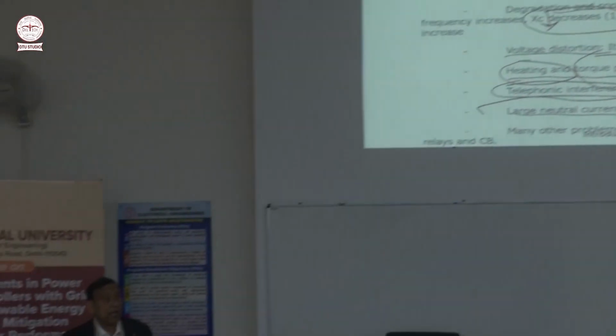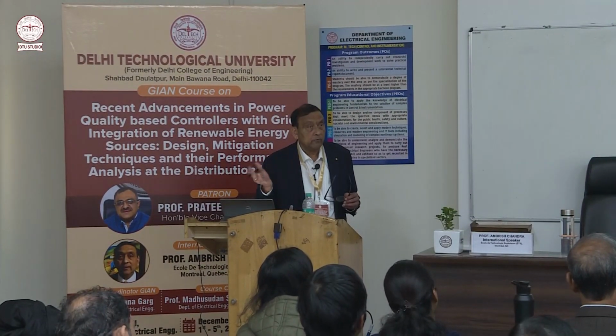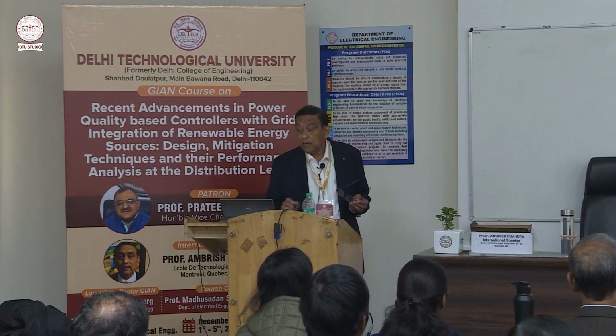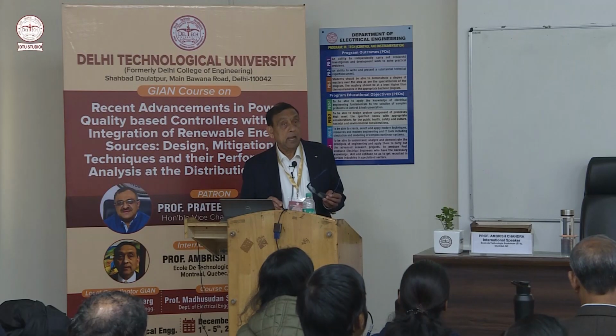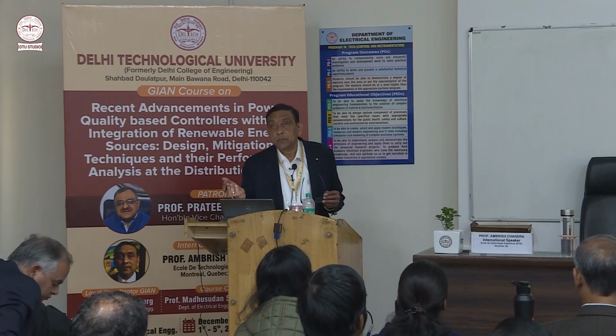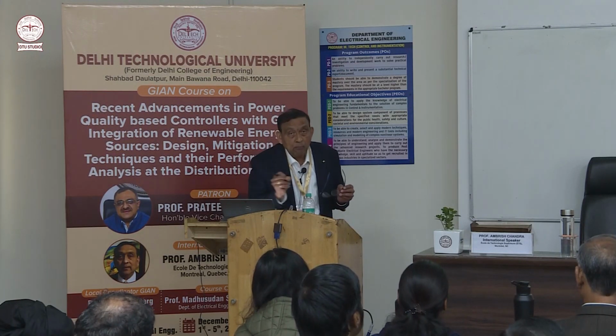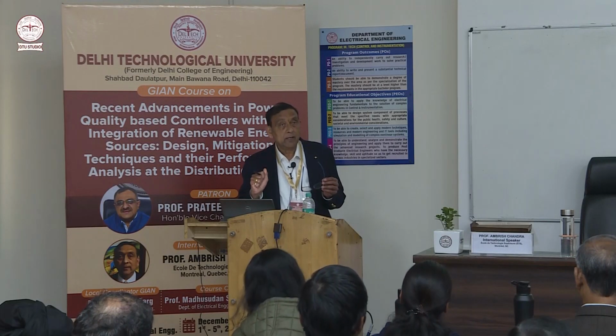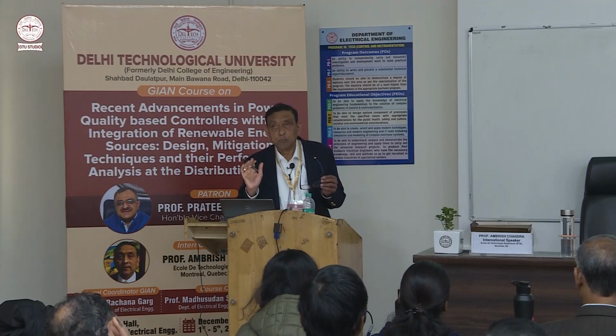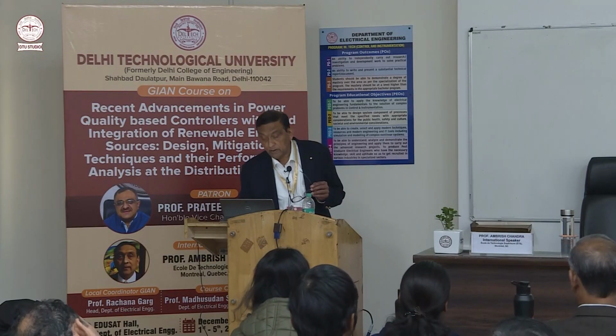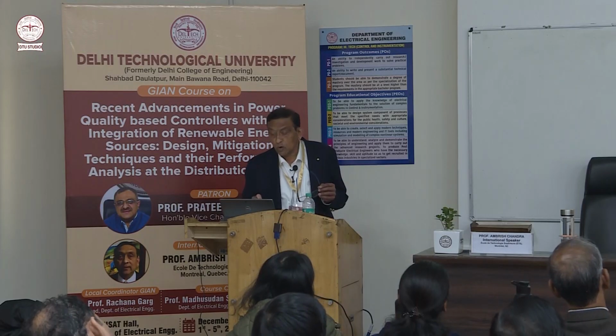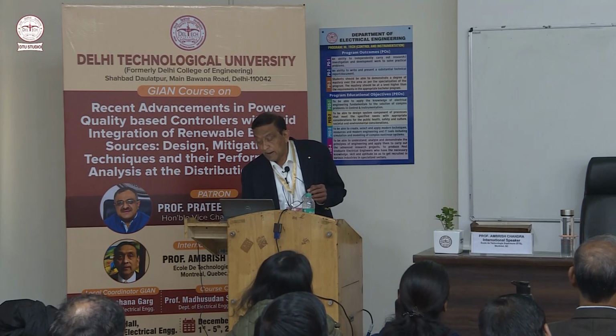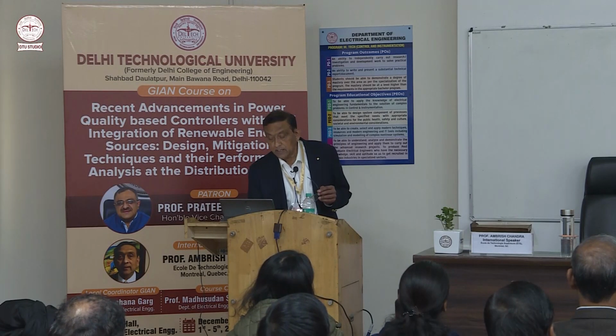So this is what happens, that if you have a non-linear load, different harmonics are generated, including the zero sequence harmonics, third, sixth, ninth, but not sixth, sixth is the even harmonic, maybe the ninth and 15th and so on, and they will add up and finally it will go to the neutral, and that neutral current may be 2 times, 3 times the rated current of the neutral cable which you have put. So that may become heated, and if the engineer does not pay attention, it may also burn out. So sometimes in the worst case it may happen. There are so many problems caused by harmonics. Many other problems, malfunctioning of energy meters and protection relays and circuit breakers. This is just one example.